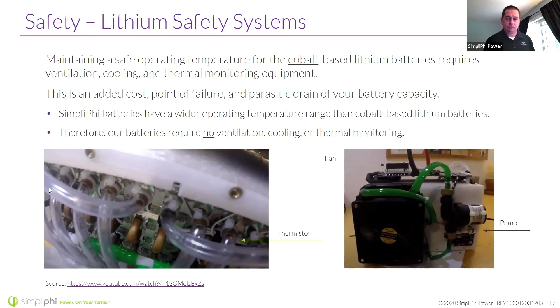But it's important to note that we don't require ventilation, cooling, or thermal monitoring. That said, your AHJ may still require it. Even though our battery doesn't need it, they may still say, hey, we want heat sensors, or hey, we want a fire suppression system. And that's really because the industry has had batteries have events, and it's given the industry a bad name. But our batteries are inherently safer and don't require this equipment.